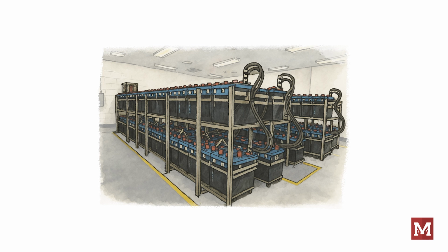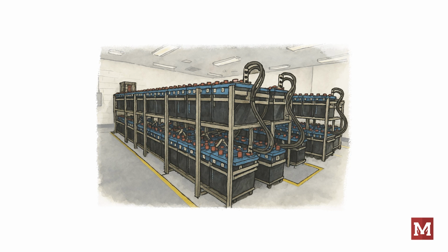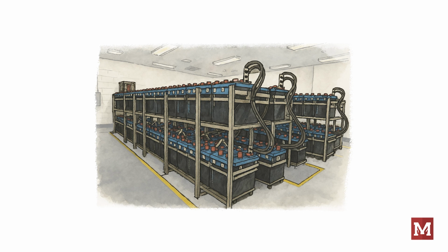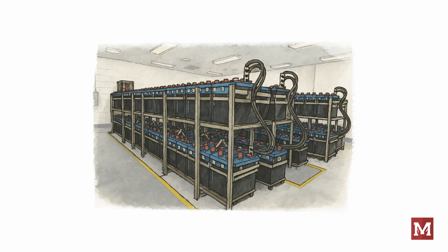Historically, most battery energy storage systems were lead acid and nickel cadmium. So, lead acid batteries are cheap, they're widely available, and simple to maintain. They have a larger footprint and are heavier than the newer technologies, but they are stable and have a long history record. They were the first generation of batteries to be used in ESS, so they have a significant portion of the market share, and they're readily available from a wide range of vendors.